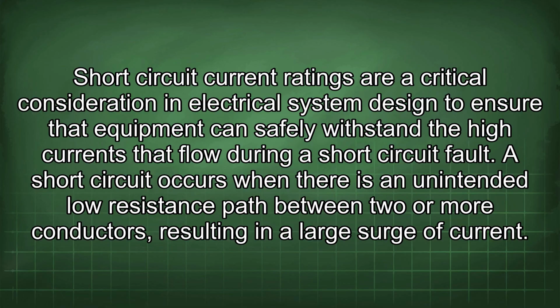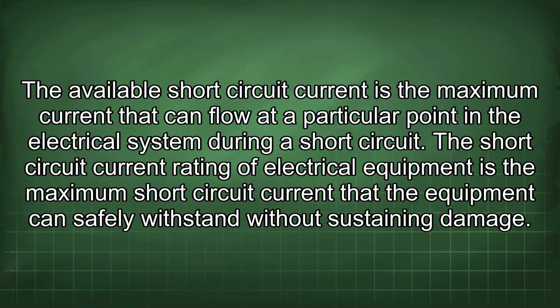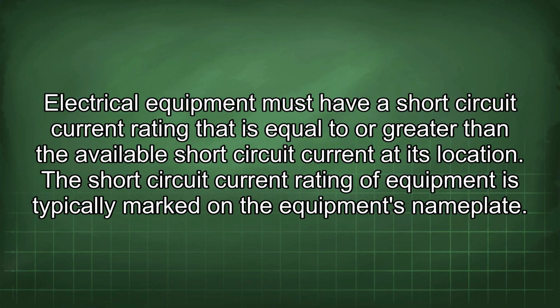A short circuit occurs when there is an unintended low-resistance path between two or more conductors, resulting in a large surge of current. The available short-circuit current is the maximum current that can flow at a particular point in the electrical system during a short circuit. The short-circuit current rating of electrical equipment is the maximum short-circuit current that the equipment can safely withstand without sustaining damage. Electrical equipment must have a short-circuit current rating that is equal to or greater than the available short-circuit current at its location. The short-circuit current rating of equipment is typically marked on the equipment's nameplate.